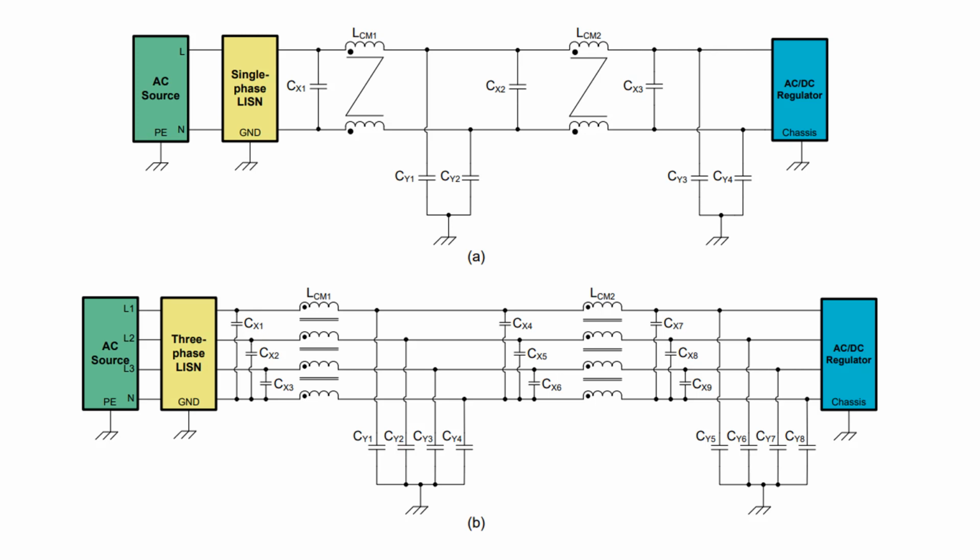Such passive filter designs rely on the insertion of high-impedance series elements, such as DM inductors or CM chokes, and low-impedance shunt elements, X and Y capacitors, to create an impedance mismatch in the EMI current propagation path. The low-order switching harmonics usually dictate the size of the reactive filter components based on the required corner frequency or the multiple corner frequencies in multi-stage designs.